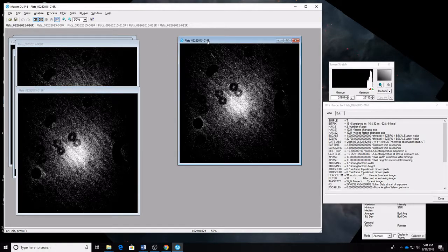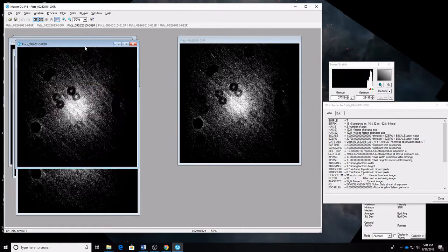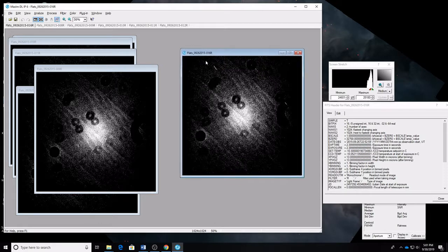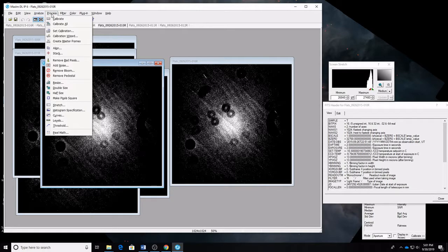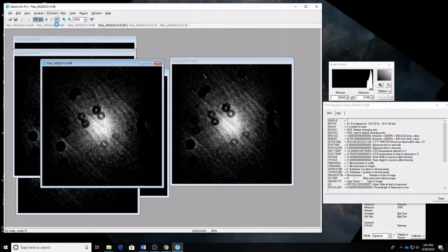Alright, so that was the 1.8, which actually is close to either of these, to the 2 or the 2.4. Maybe we can just get away with doing all of them in one shot, since we don't have 2.4s either. We don't have 2.4s and we don't have 2s. So let's just go ahead and say process calibrate all. It's thinking about it. It has to think longer when it does more math. It's removing the bias signal first, and then it is averaging the darks together, and then it is also applying the bias separately to this because the electronic noise was still in this.